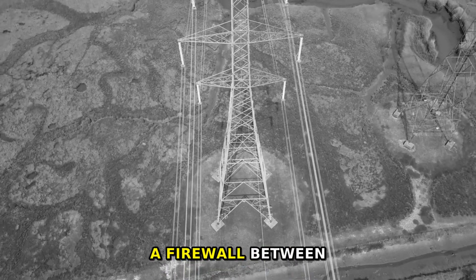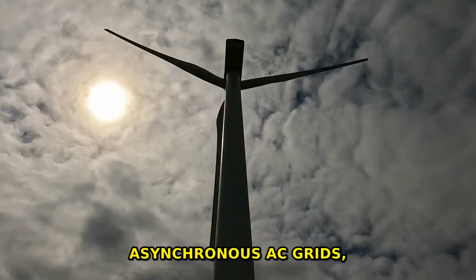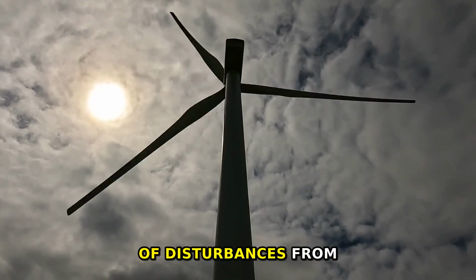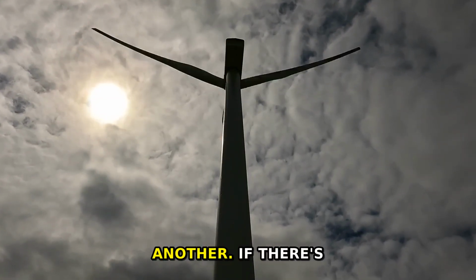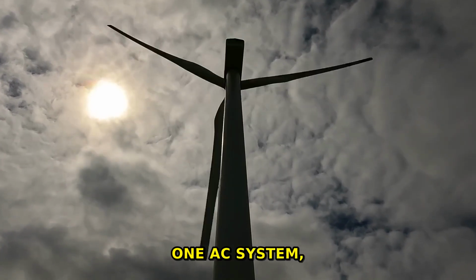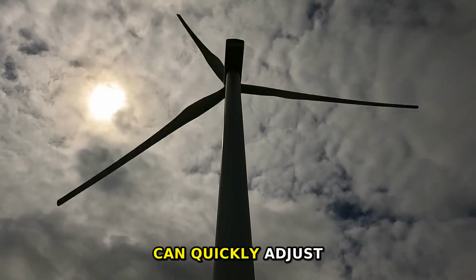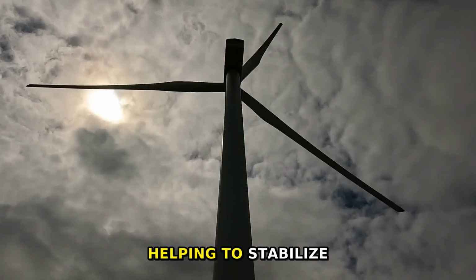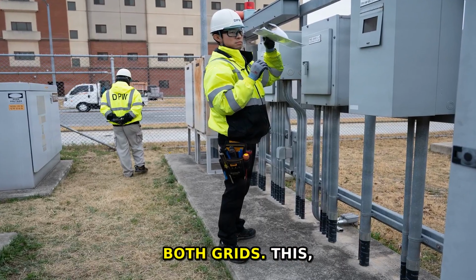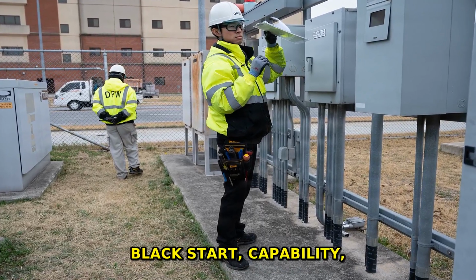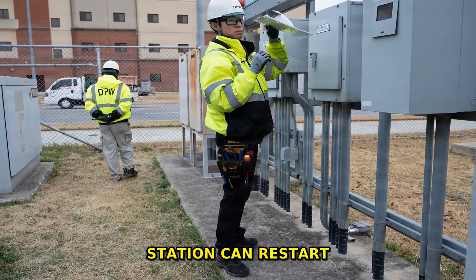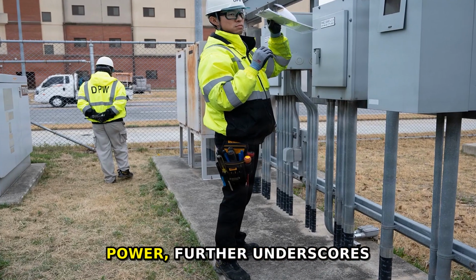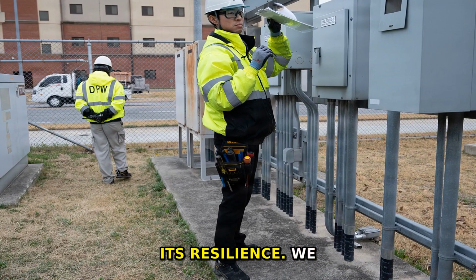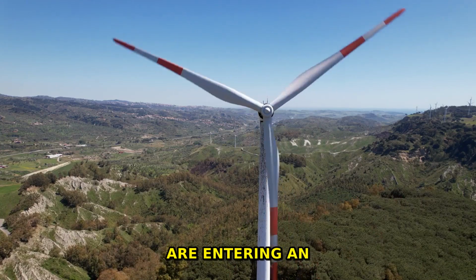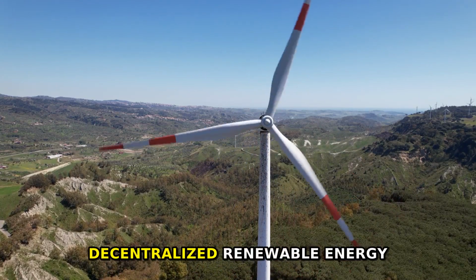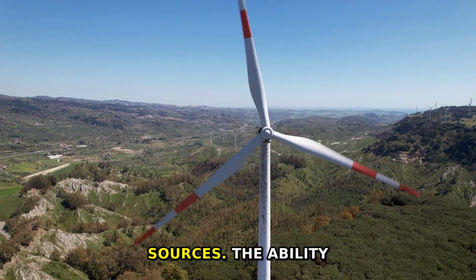HVDC links act as a firewall between asynchronous AC grids, preventing the propagation of disturbances from one grid to another. If there's a fault in one AC system, the HVDC link can quickly adjust its power transfer, helping to stabilize both grids. This black start capability, where a converter station can restart an entire grid segment without external power, further underscores its resilience. We are entering an era of global grids, powered by decentralized renewable energy sources.